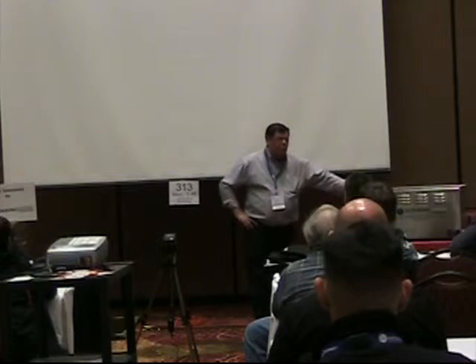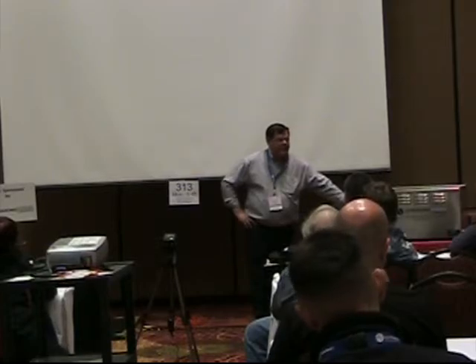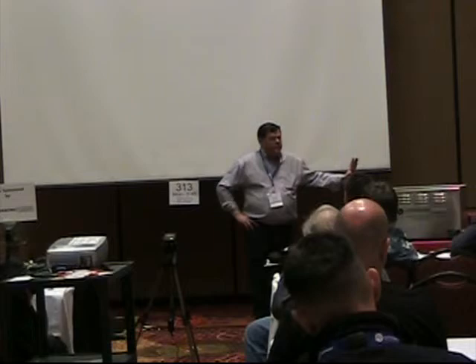I have an issue with this machine right now, but that's not the machine's fault. I've got an idiot in the parts room who won't rinse the instruments off away from the machine, and all the controls in the front have constantly gotten wet, to the point that he put a piece of plastic over it thinking that would help. I'm sure this switch is shorted out right now, because when I turn the power on, the power's working, all the transducers and the generators are plugged in.